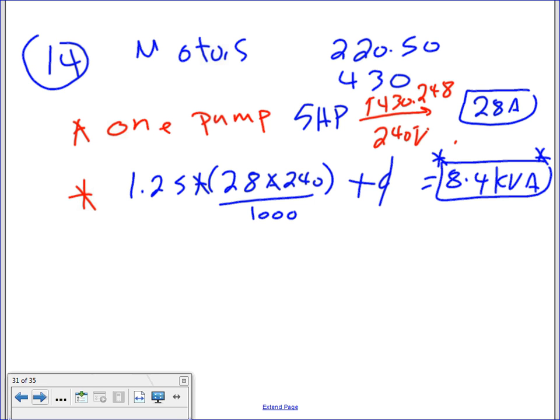So this baby will be seen as an 8.4. Anybody know why I multiplied 28 times 240 divided by 1,000 to make kVA for one motor? Why did I increase 1.25 on it, guys? Because you take the largest motor, multiply by 1.25. What's with the 0 here? There's no other motors sharing the same feeder. Were you timesing by 0 or adding by 0? Adding by 0. Oh, you don't multiply it by 0. You add the kVA for the other motors, which is 0. So that's the motors. If there are 4 motors, you take one of them, up it 25%, add the other 3. Ladies and gentlemen, we're almost done.